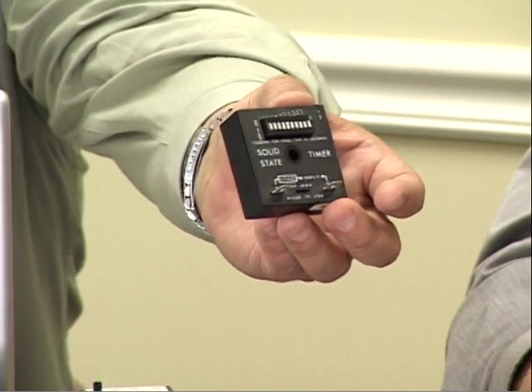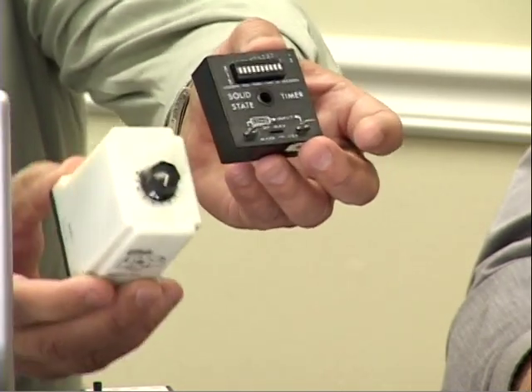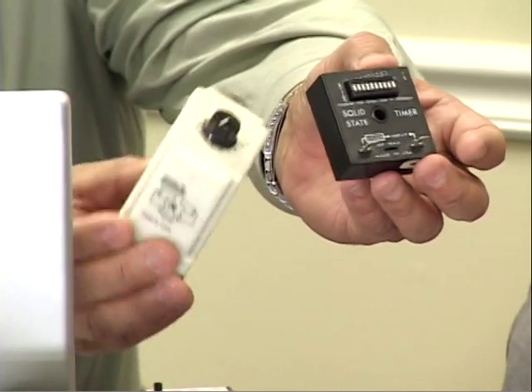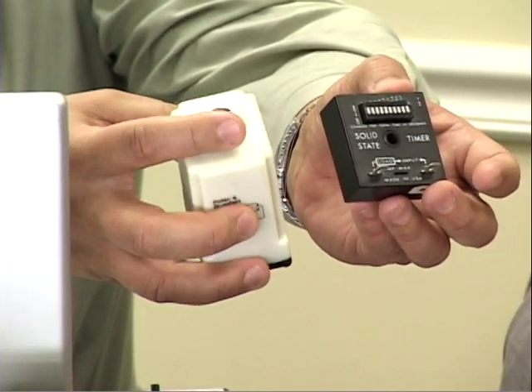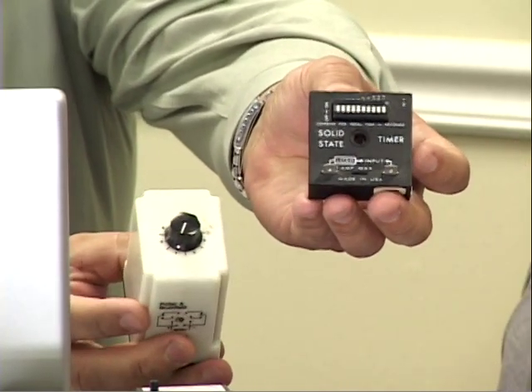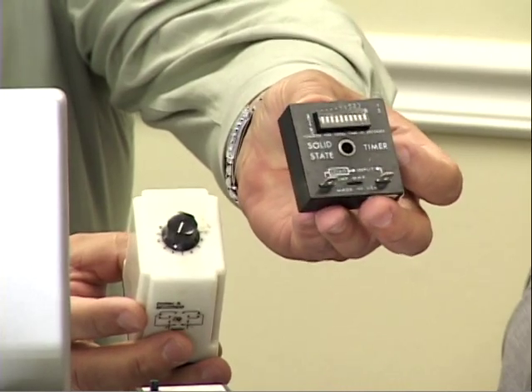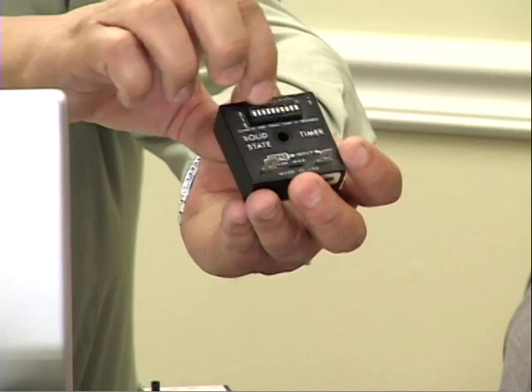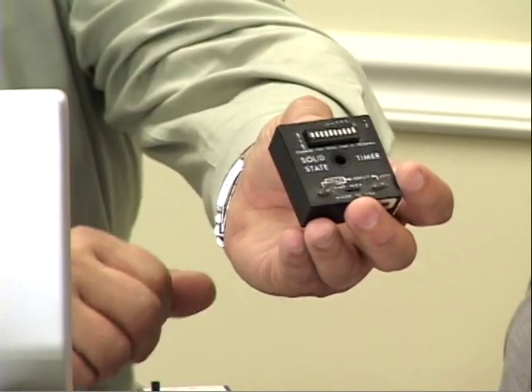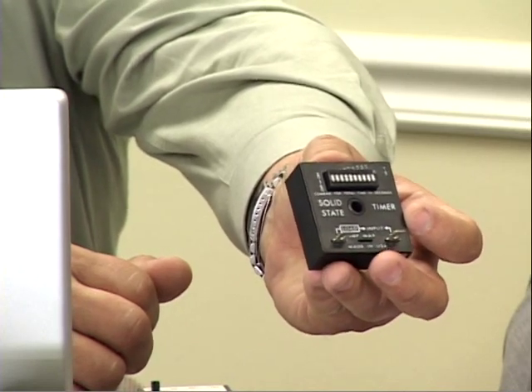Well, this might be where you introduce that time delay. You could either use a time delay relay like this, the white button, and adjust the time delay here, or you could use a standard relay with a solid-state timer. And how do you adjust that solid-state timer? There are switches here. Little dip switches. The instructions say that this and this and this gives you this and this time. Correct. All right. Now, is one called analog? Is the one that you can turn analog? That one right there, or not really?